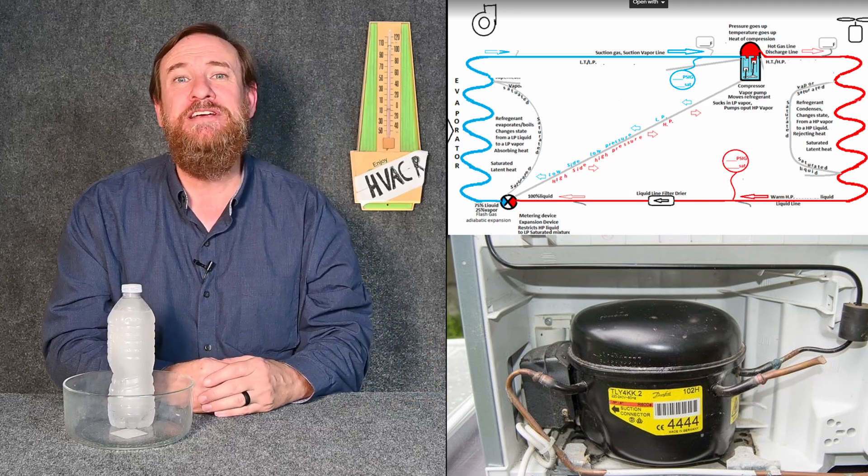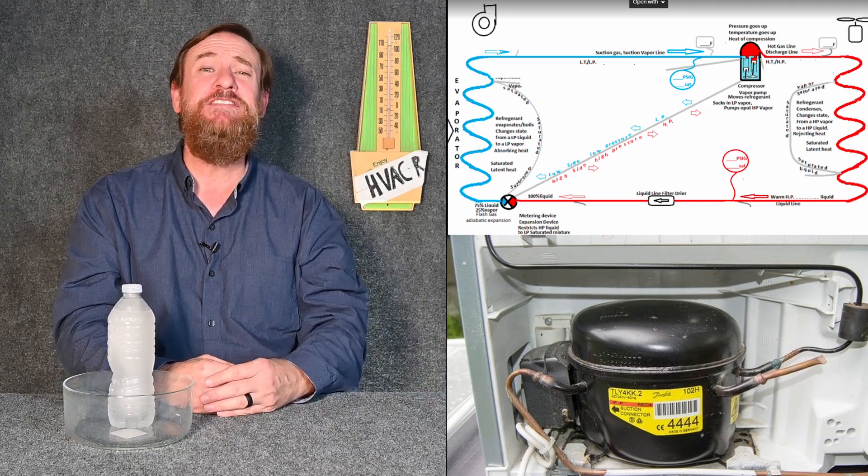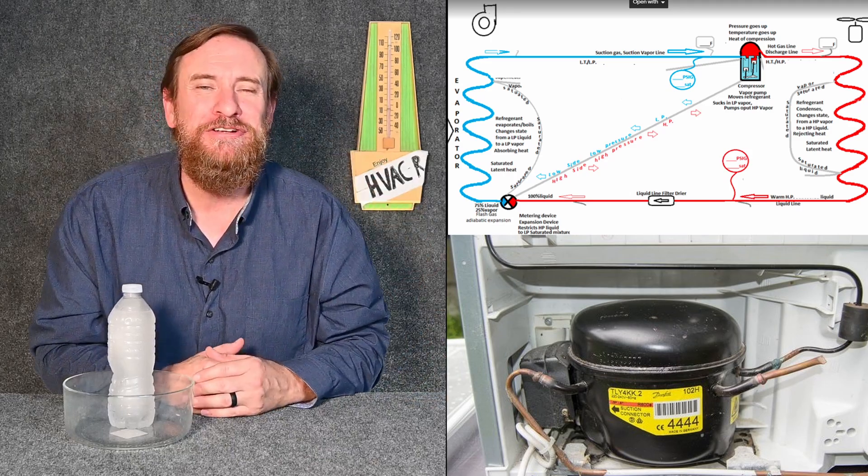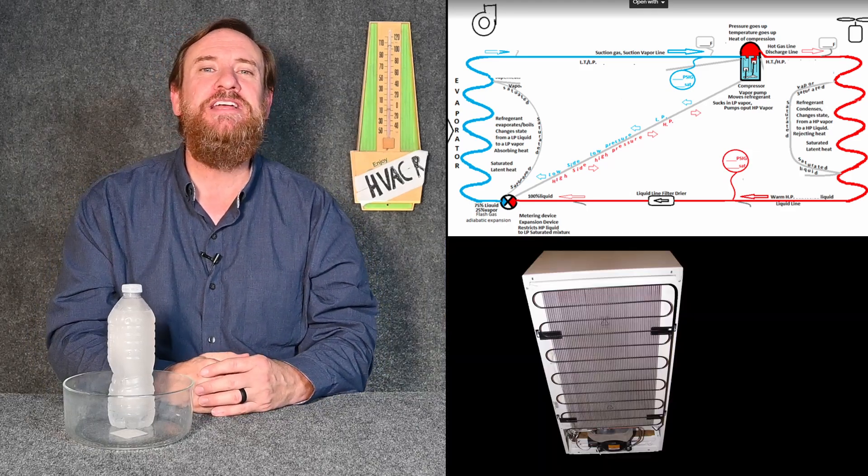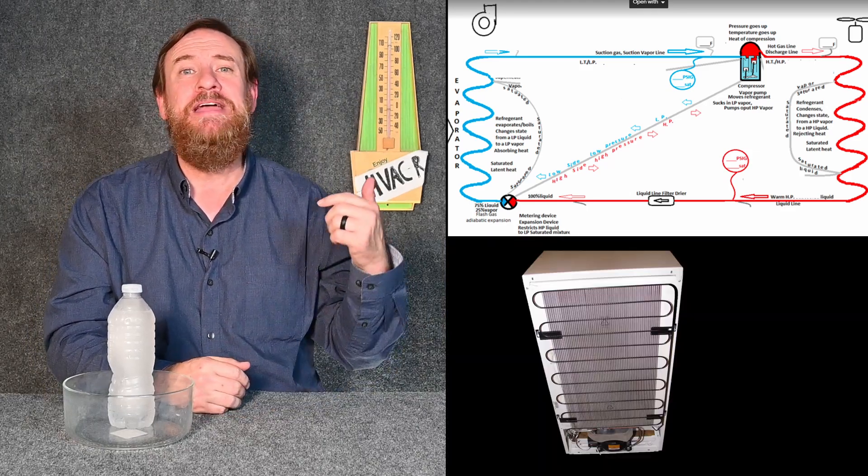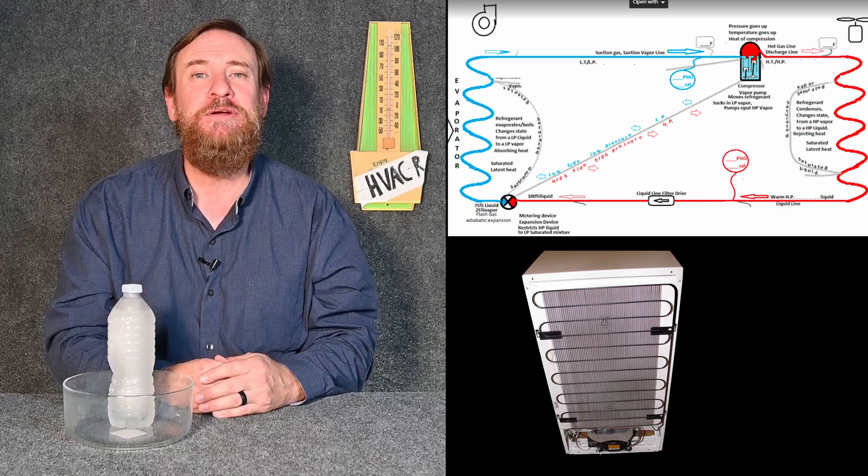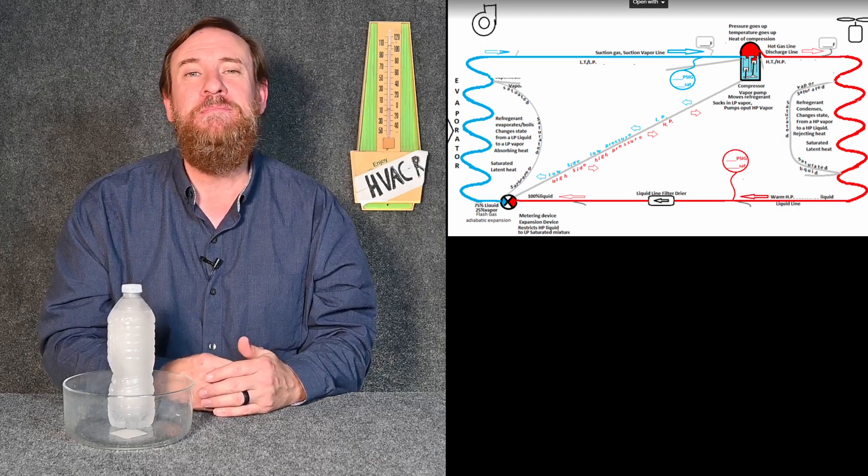We then go to the compressor. We raise it from a low-temperature, low-pressure superheated vapor to a high-temperature, high-pressure superheated vapor. And then we put it through the condensing coil. We desuperheat, make that refrigerant change state from a vapor to a liquid. And then we sub-cool that liquid back to the metering device.